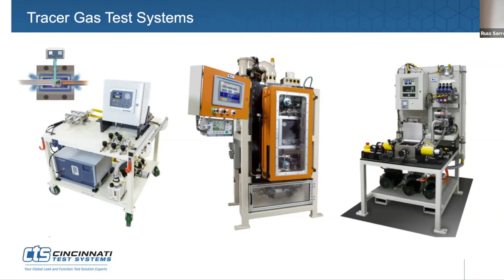Some of the main reasons that we would apply tracer gas to an application is that maybe it's very high pressure with a low leak rate, or it could be low pressure with a low leak rate. But it's really the leak rate that is a big determining factor. And the beautiful part of tracer gas is that the impact of thermal change on the test is not even a concern, as opposed to mass flow and pressure decay technologies.